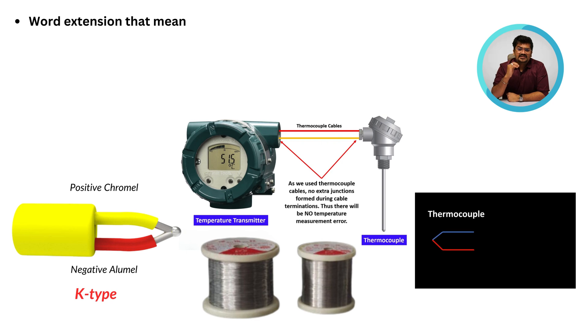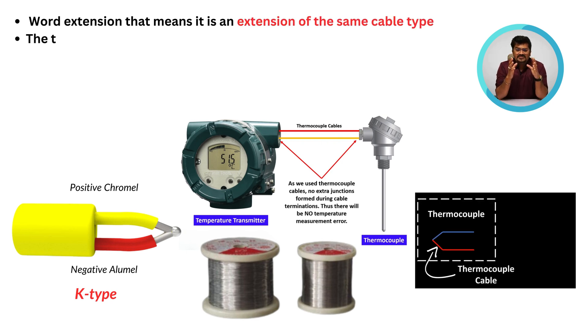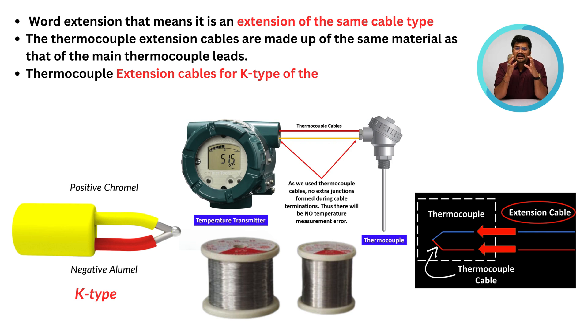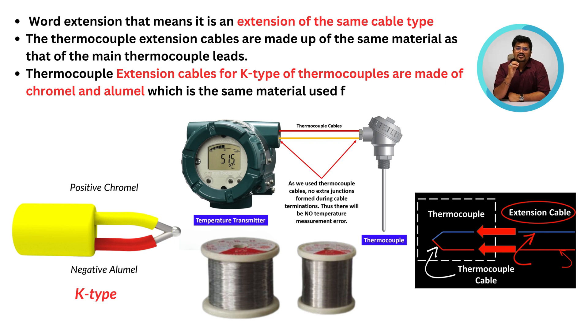Let's understand the extension cable. From the word extension, that means it is an extension of the same cable type. The thermocouple extension cables are made up of the same material as that of the main thermocouple leads. Thermocouple extension cables for K-type thermocouples are made up of Chromel and Alumel, which is the same material used for the construction of K-type thermocouples.